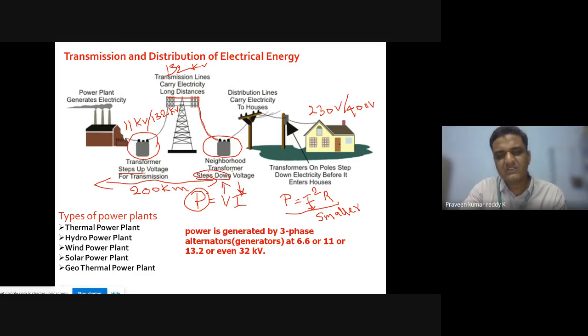Customer requires all the equipments of the customers are designed to operate on 230 volts. So I have made it 132 kV stepped up, so again I have to step down it. I will use a step down transformer at the receiving end at the customer end. This steps down the voltage, step down transformer like 132 to maybe 33 kV. I will reduce it to 33 kV or 66 kV. First I will step down to one level 66 kV or I can reduce it to 33 kV. It cannot be done at one step. I will use step by step reduction. Then I will have some other distribution transformers where I will again reduce it to 11 kV and from 11 kV I will step down it to 400 or 230 volts.